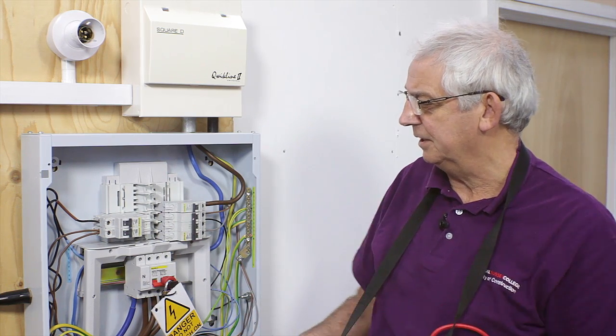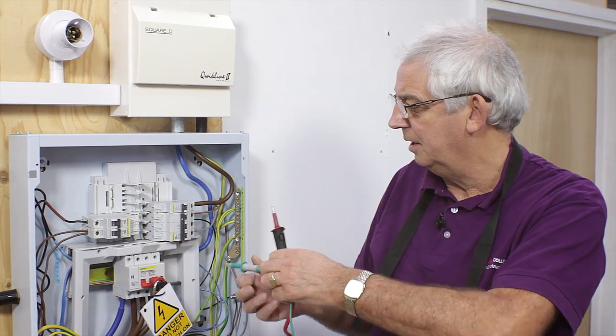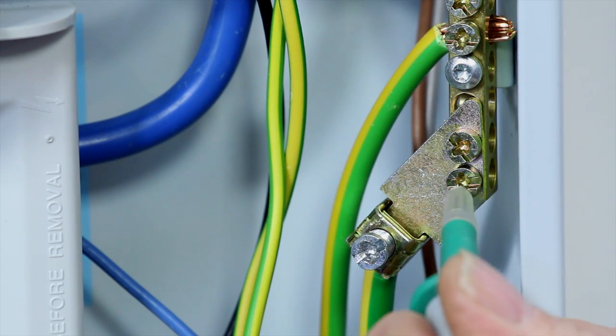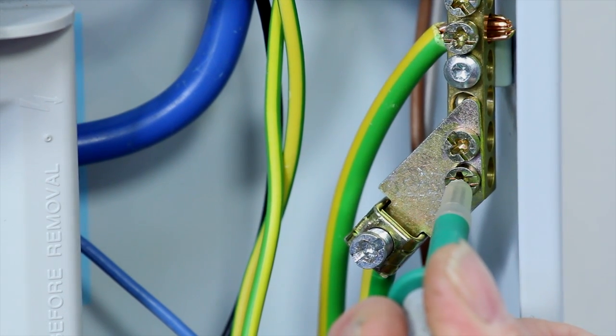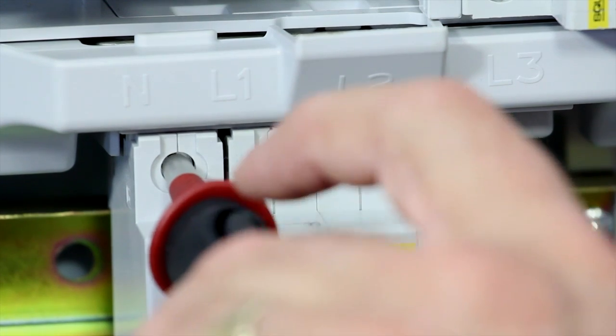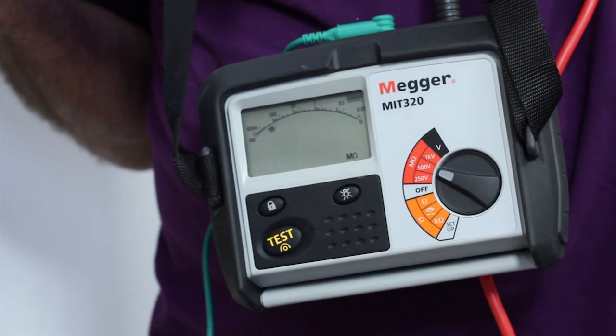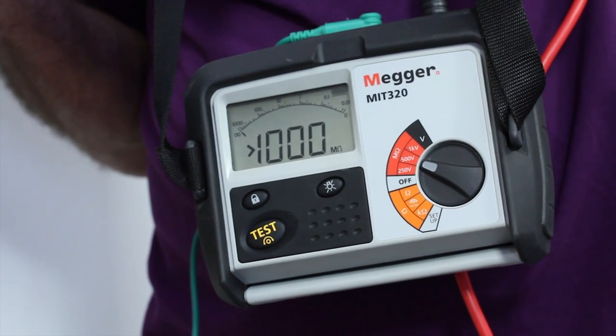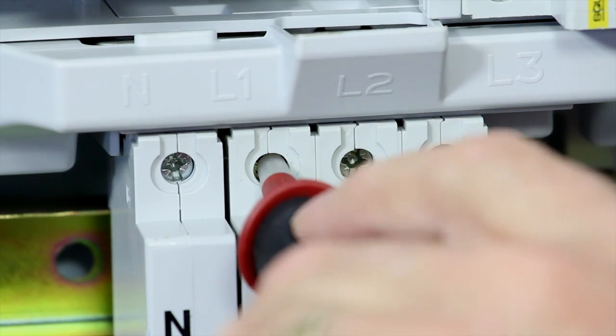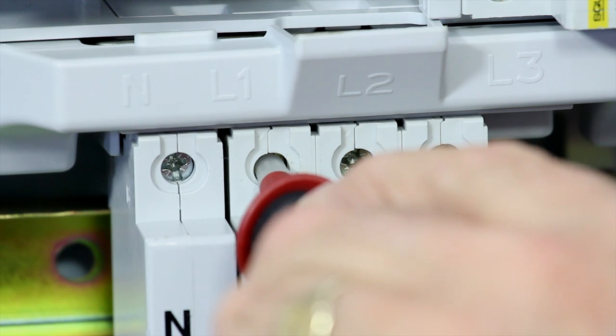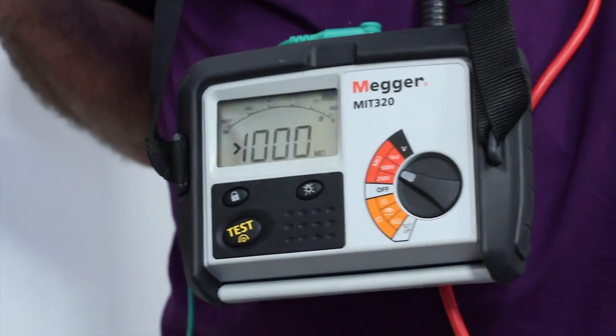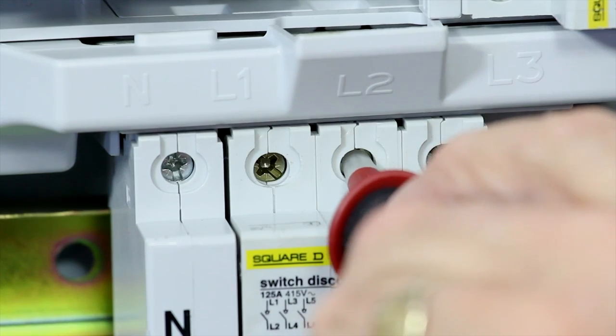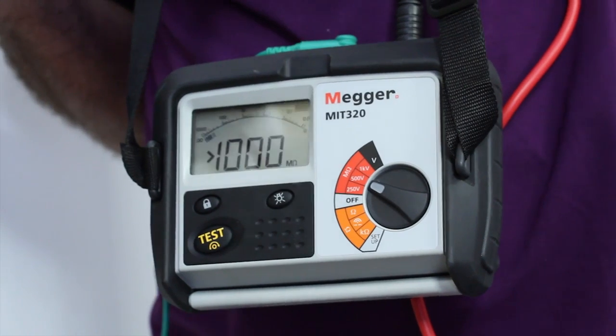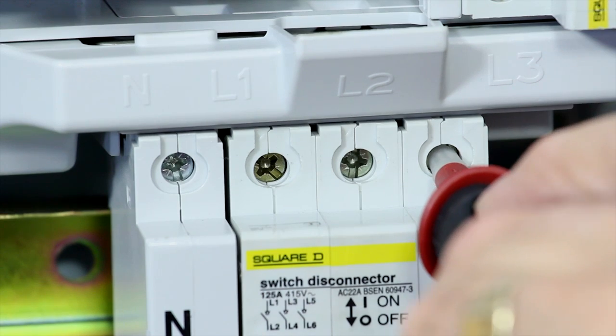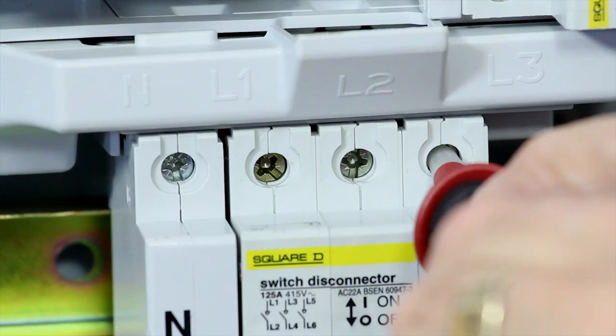The other test I need to do, of course, is between all live conductors and earth. So make sure the probe's secure onto an earth point, test between neutral and earth, should be over range. L1 to earth, again over range. L2 to earth, again over range. L3 to earth, again over range.